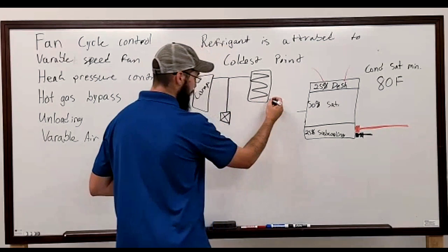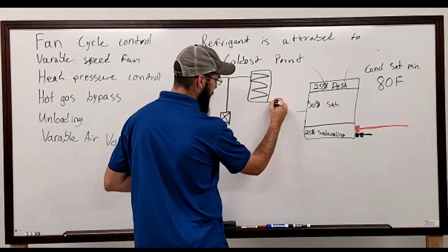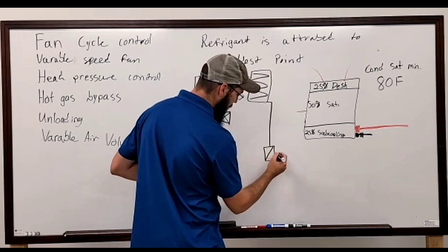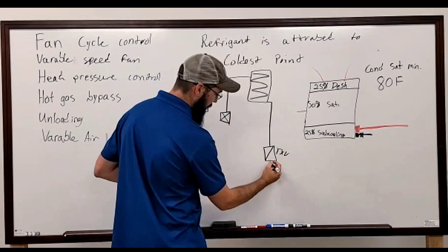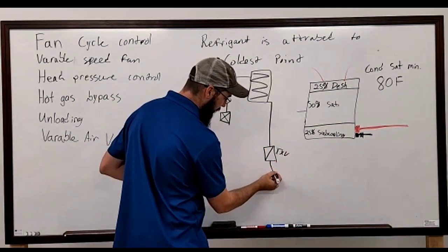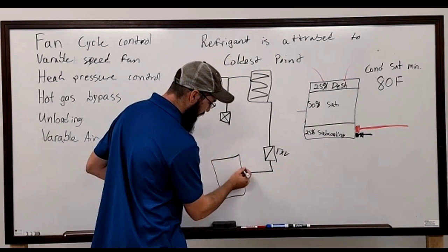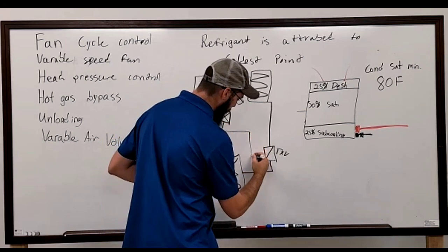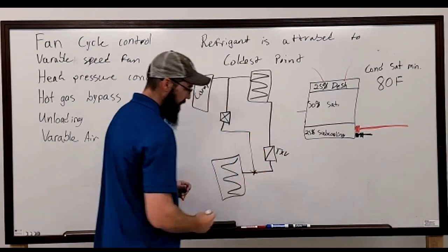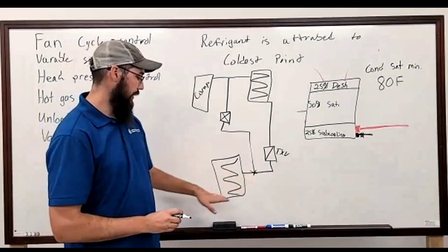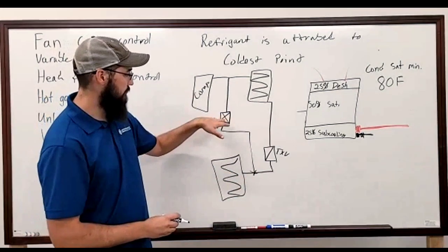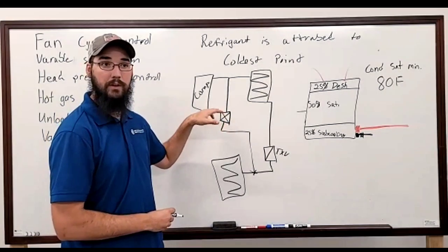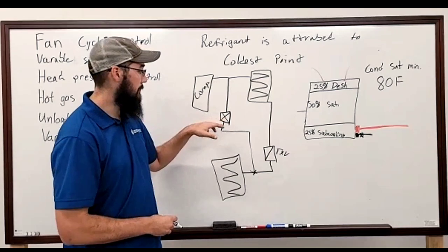So what'll happen is we come out of the condenser, we hit the TXV, and then we come out of the two-phase line. We come over to our evaporator. This will pipe over and land right here, in your two-phase. Suction lines come over here and up. This is trying to monitor so much differential between these. These will also be adjustable. All right?